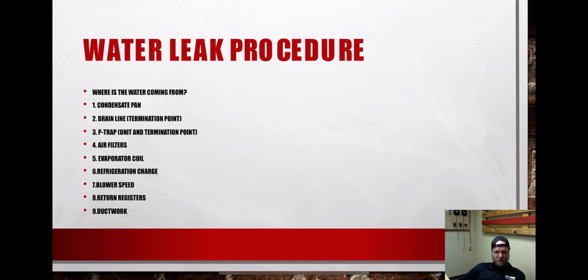Why? Because the units start condensating more, and the lines that are plugged a little bit are not able to handle that amount of flow. So sometimes you do get up to it and they're not leaking at that time. That will happen because either you got there in the morning or it's satisfied, and so you just gotta clean those lines out. But first things first, you come up on a water leak.